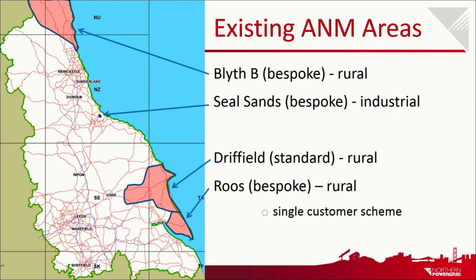The Seal Sands area is just looking after a very small industrial zone, but again, it's got quite a lot of generation in there, about 190 MVA of generation on 2 transformers, and if we lose one transformer, we immediately need to get down to 90 MVA, and that's being managed on an inter-trip type scheme rather than controlling the set point. We actually have to throw generators off in those circumstances. But again, same principles, last in, first off. So there's a sequential tripping scheme there based on the amount of overload that occurs.